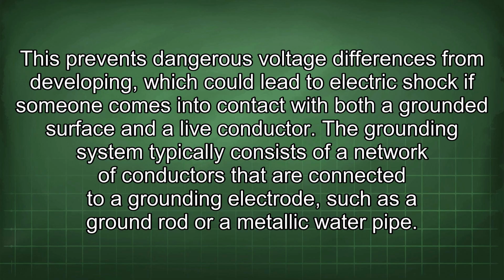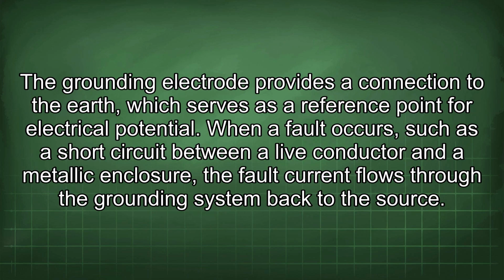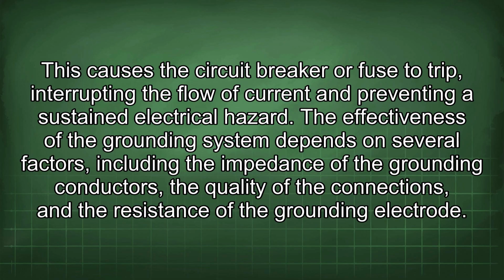The grounding system typically consists of a network of conductors that are connected to a grounding electrode, such as a ground rod or a metallic water pipe. The grounding electrode provides a connection to the earth, which serves as a reference point for electrical potential. When a fault occurs, such as a short circuit between a live conductor and a metallic enclosure, the fault current flows through the grounding system back to the source. This causes the circuit breaker or fuse to trip, interrupting the flow of current and preventing a sustained electrical hazard.